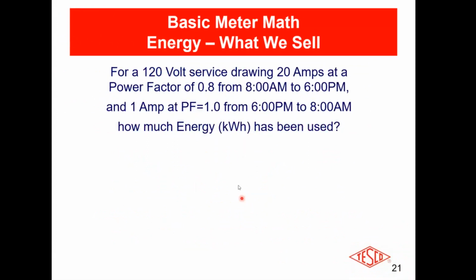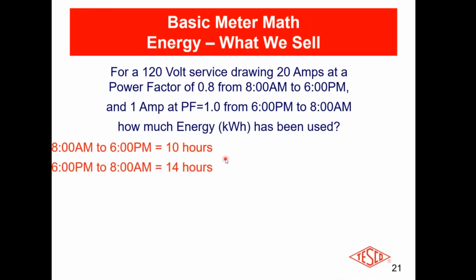Now, here's a more practical situation where I'm drawing it during the day when the plant's going. I've got a horrible power factor of 0.8, and I'm drawing most of my power then, and it's from 8 to 6 that I'm doing this. That's the average that I'm pulling. At night, I'm using a lot less, but my power factor jumps up to 1. That's a fairly typical scenario. So how much energy is being used?